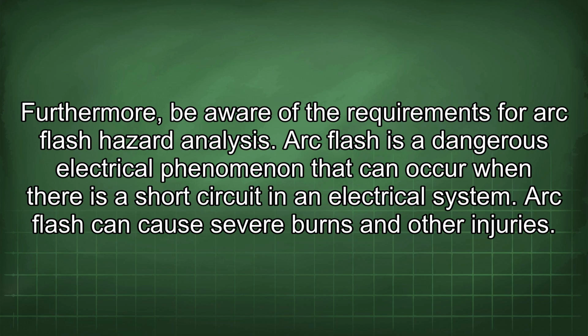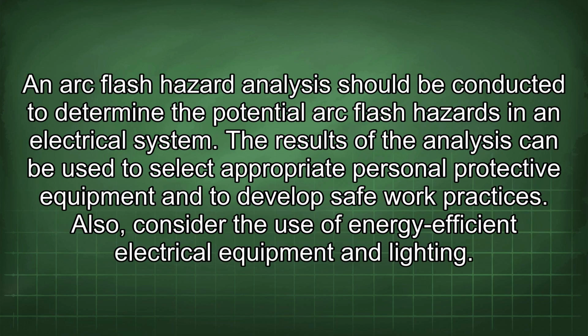Furthermore, be aware of the requirements for arc flash hazard analysis. Arc flash is a dangerous electrical phenomenon that can occur when there is a short circuit in an electrical system. Arc flash can cause severe burns and other injuries. An arc flash hazard analysis should be conducted to determine the potential arc flash hazards in an electrical system. The results of the analysis can be used to select appropriate personal protective equipment and to develop safe work practices.